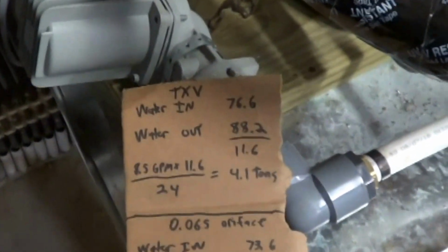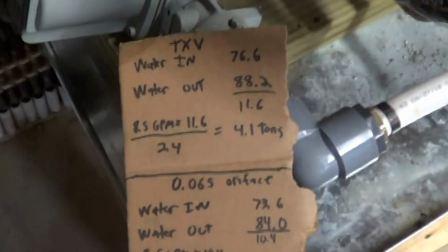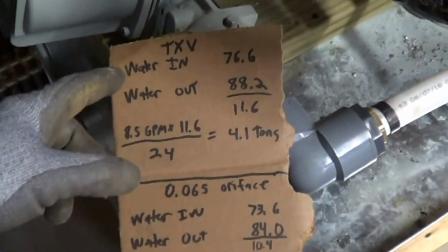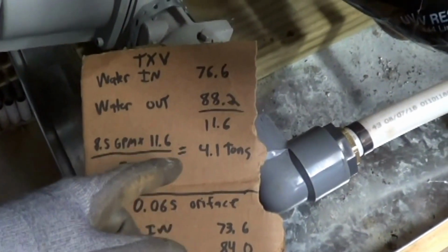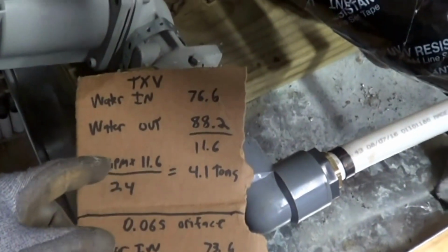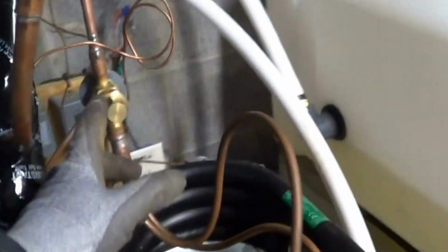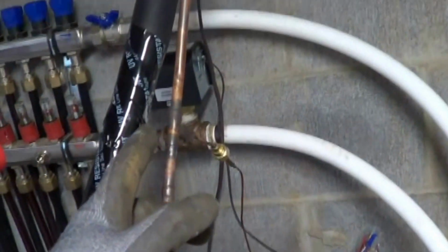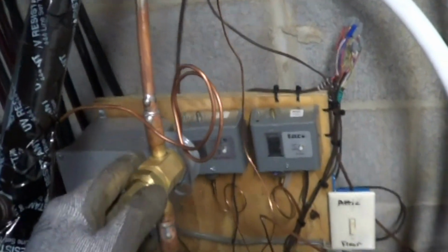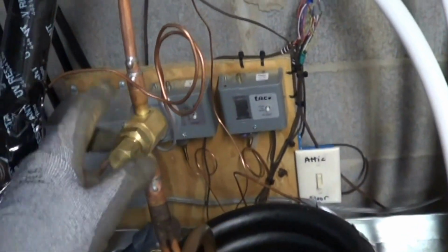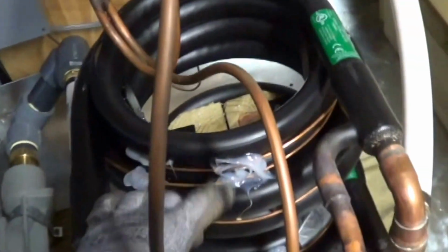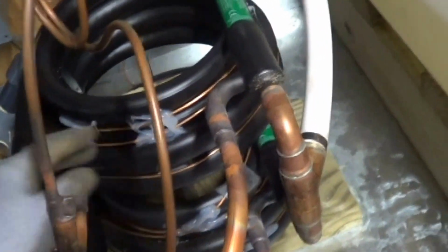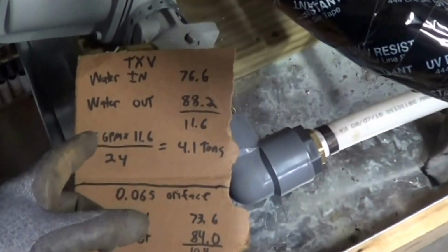So I tried putting an expansion valve outside because I knew I could get more capacity having an expansion valve on the condenser coil, and it did 4.1 tons, but I ended up tripping on high head pressure again. And the reason why is the liquid feeding out. Expansion valves hunt. This valve's not used, it's just used on the cooling cycle. But on the heating cycle, as soon as that valve closed off, they would end up backing up the refrigerant in this coil and then get a nuisance trip on the 500 pounds. So I did have to pull the expansion valve back out.